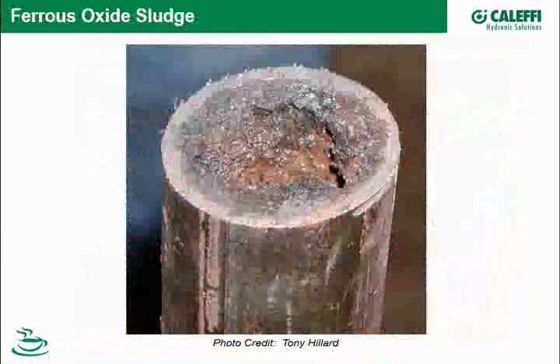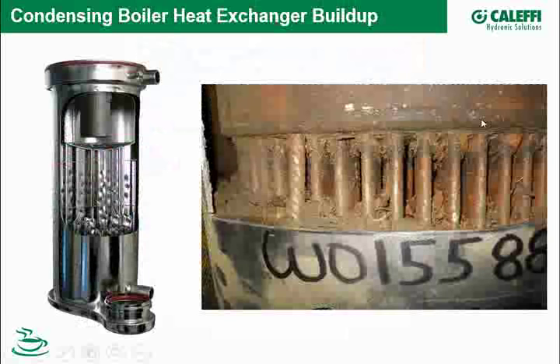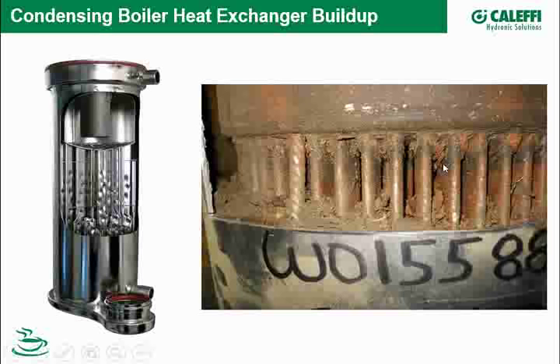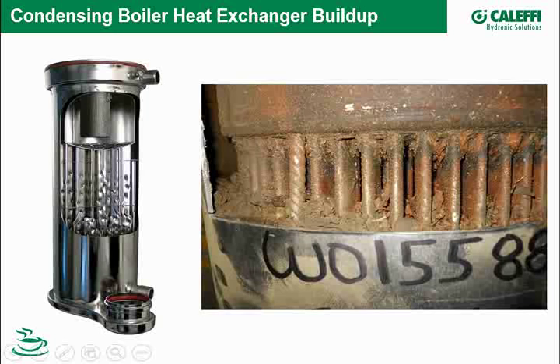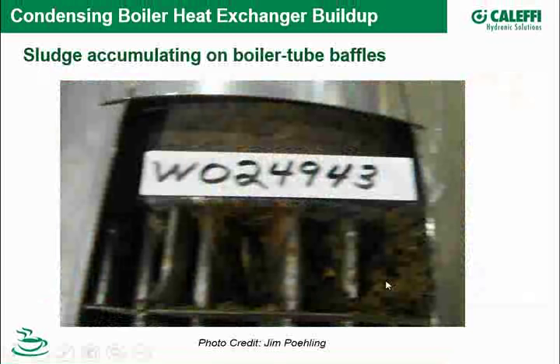To continue with problems — a commercial condensing fire-tube boiler. Here's a cutaway showing the same type of boiler affected by a concoction of iron oxide along with what appears to be scale, indicated by red and white coloration. Here's another shot showing darker sludge — probably a higher mix of oxide — that caused a failure. Jim Poehling from First Supply was a guest host on water quality and this photograph illustrates the problem well.